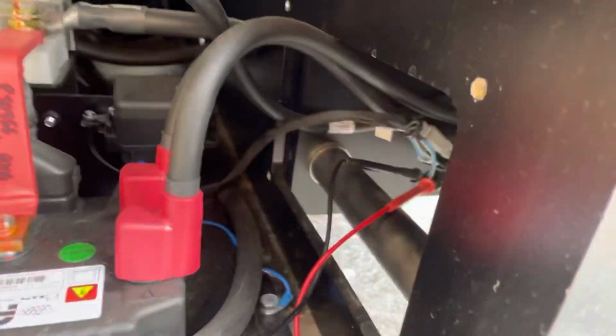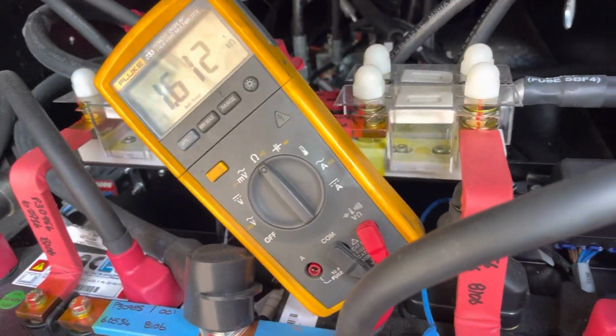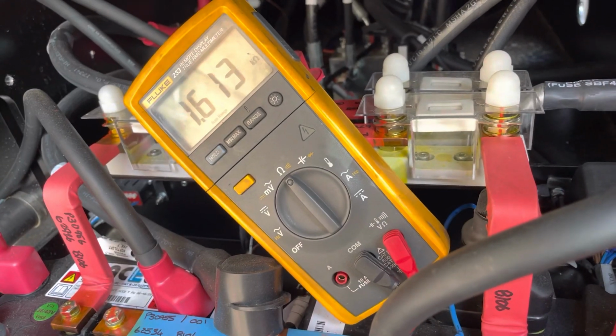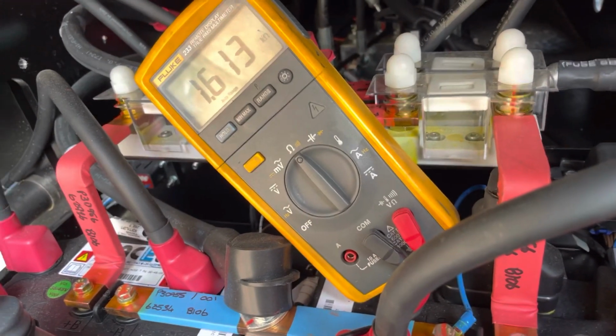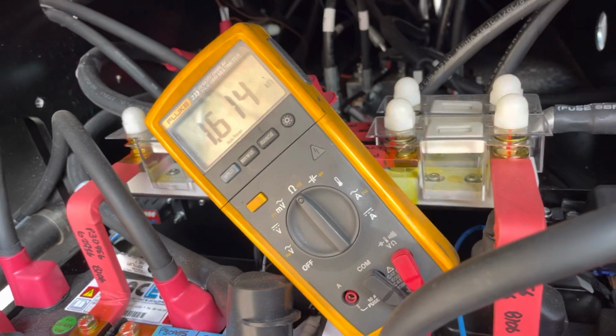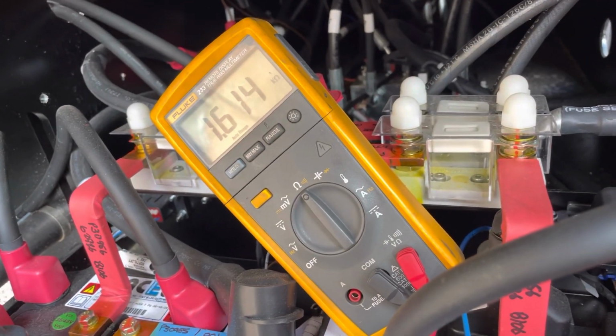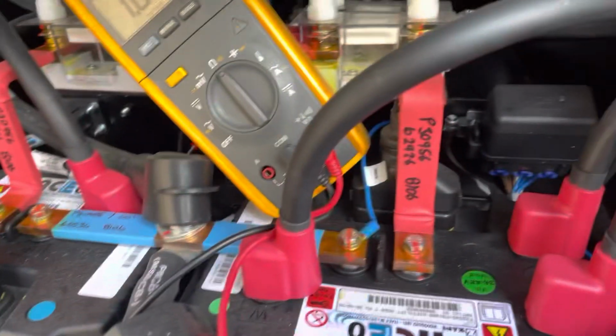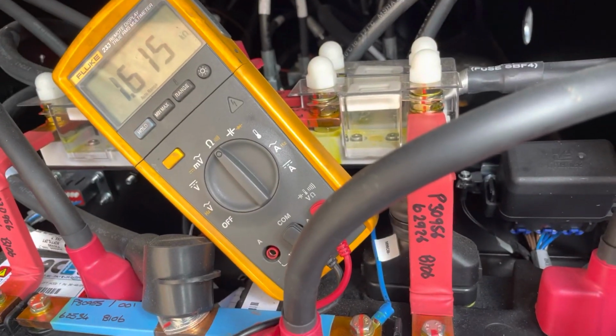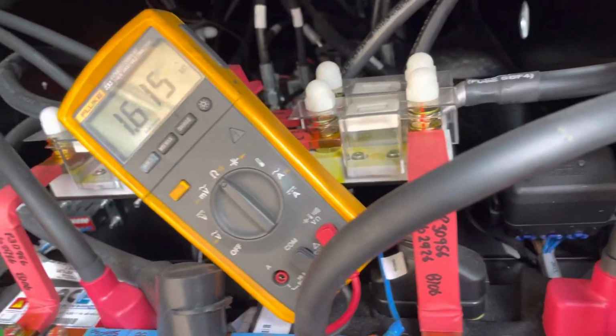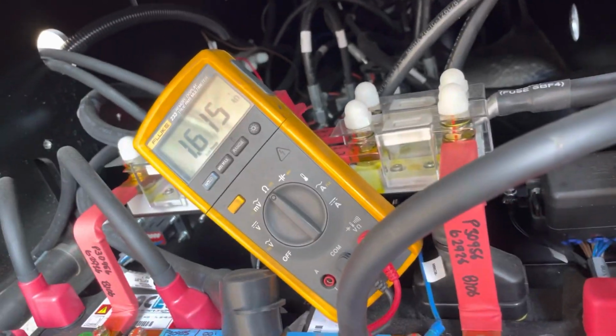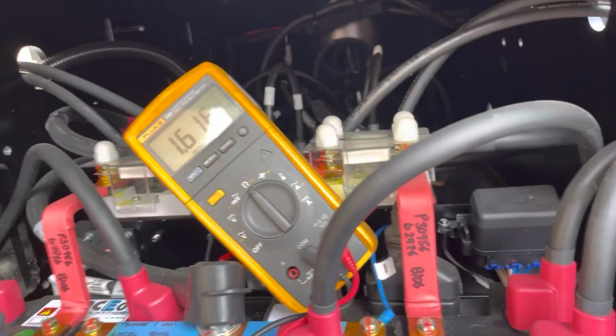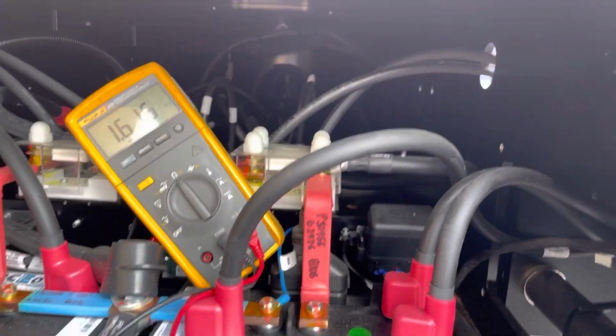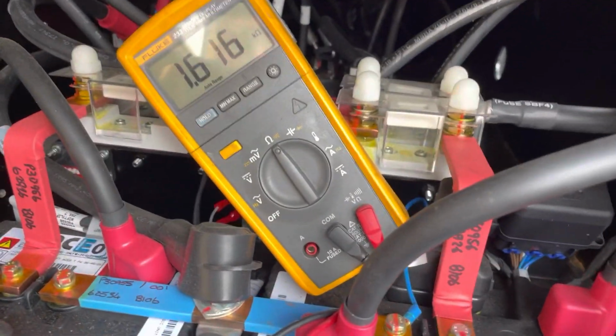So if something happened with the sensor, I will try to move the wire just to see if that's going to make any difference, or it may not, but something is not right with the sensor. That's why we're getting the error and it's not giving the fast drive. Okay, so it seems like moving wires doesn't make any difference. So it's most likely the problem with actually the sensor itself.